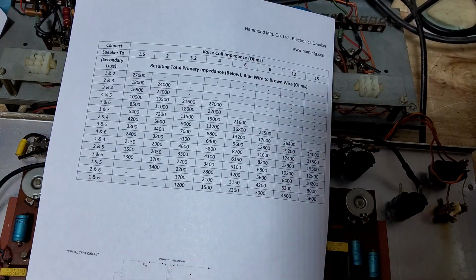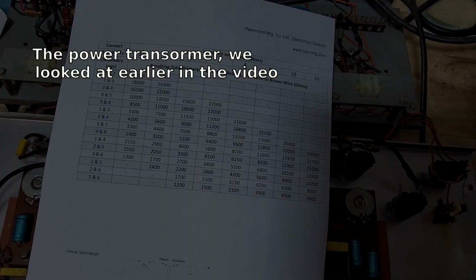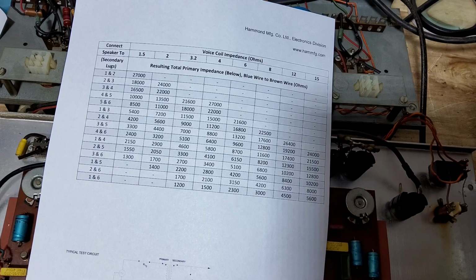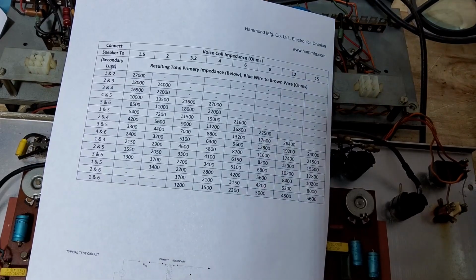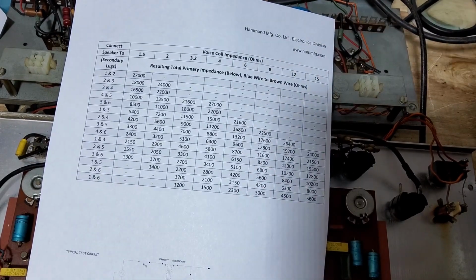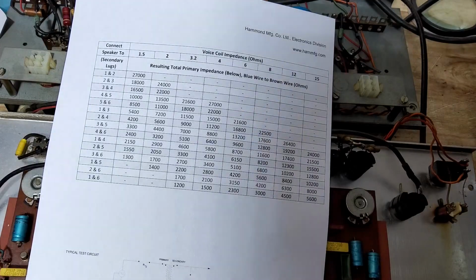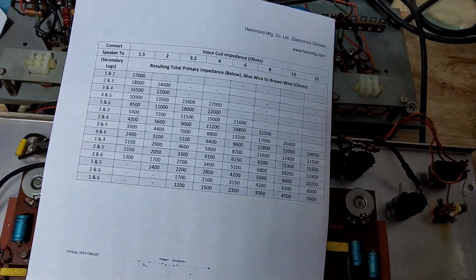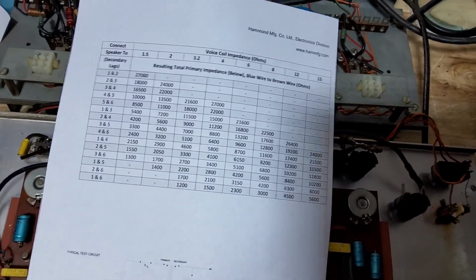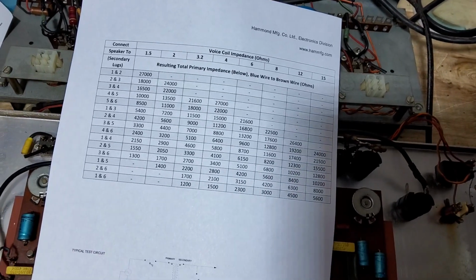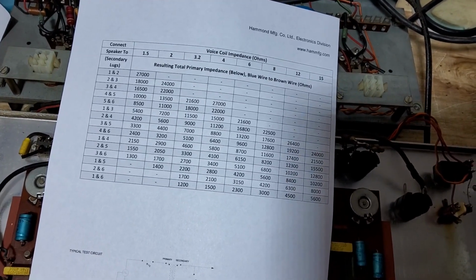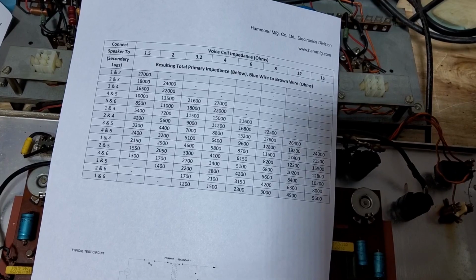I tested the transformer and put 240 volts in, and got 262 out - that's 366.8, 367 volts. Now we'd expect that to drop down probably 40 to 50 volts, so let's say 40 for the sake of it. So that's going to be around about 326.